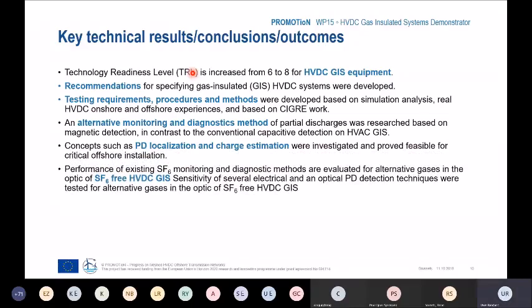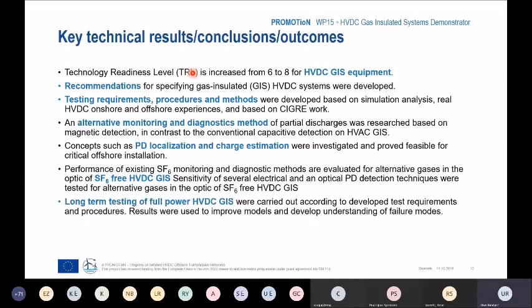Moreover, we have performed a lot of partial discharge tests with different defects using alternative gases and have compared the results with SF6. As an outcome, we can say that from that point of view, there is no reason against the use of other gases for HVDC in gas-insulated switchgear. And moreover, it's possible to use the same diagnostic and monitoring tools for these new gases. We have finished the long-term test of the full-powered HVDC GIS according to the developed test requirements and procedure.